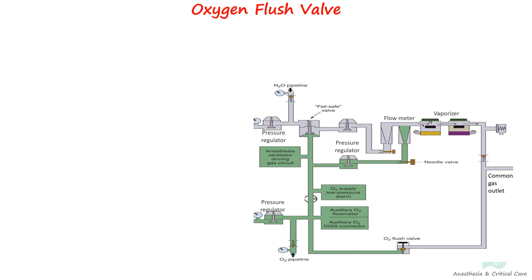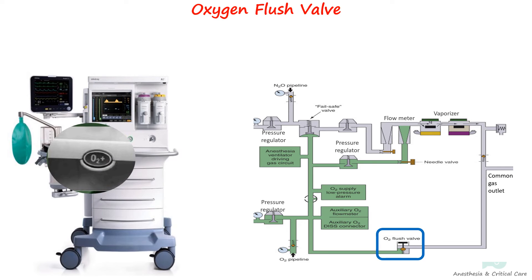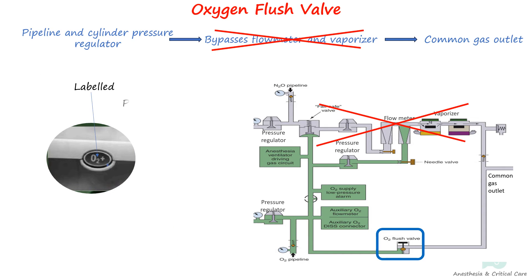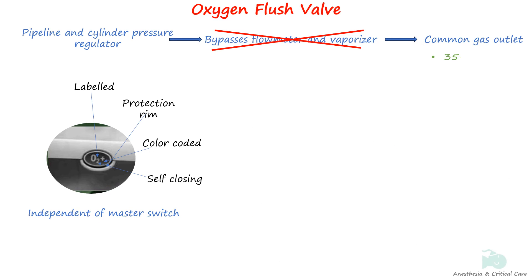The oxygen flush, also known as the emergency oxygen bypass, receives oxygen from the pipeline inlet or cylinder pressure regulator and directs a high, unmetered flow directly to the common gas outlet. It is commonly labeled O2 and mounted on the front of the machine for easy accessibility. The self-closing, color-coded flush button is commonly recessed or placed in a collar to prevent accidental activation. The oxygen flush can be activated regardless of whether the master switch is on or off, providing flows of 35 to 75 liters per minute at approximately 60 psig directly to the common gas outlet, bypassing the flow meters.